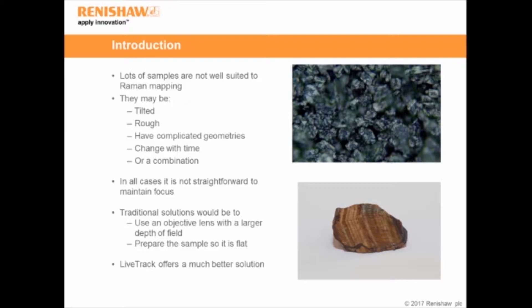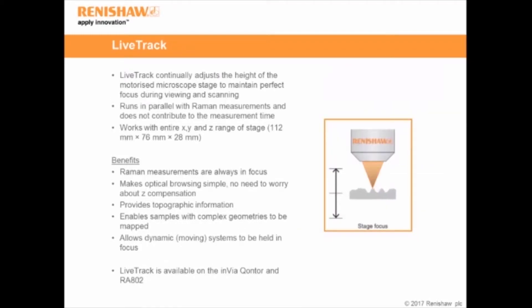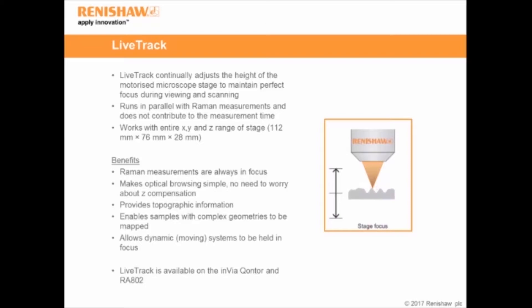What I'd like to show you now is how LiveTrack, our new autofocus technique, offers a much better solution than these two. LiveTrack continuously adjusts the height of the motorised microscope stage to maintain perfect focus during both viewing and scanning of the sample. This is highlighted in the animation on the right-hand side — whereas before I would be out of focus, now it nicely tracks the surface during measurements.